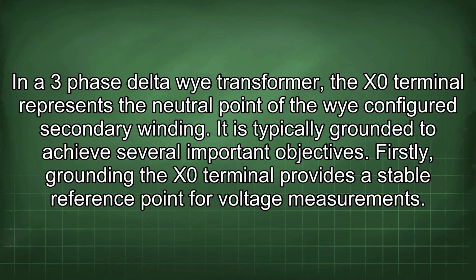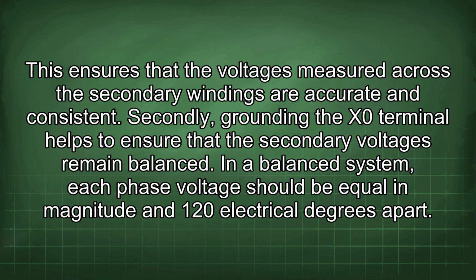In a three-phase delta-Y transformer, the X0 terminal represents the neutral point of the Y-configured secondary winding. It is typically grounded to achieve several important objectives. Firstly, grounding the X0 terminal provides a stable reference point for voltage measurements. This ensures that the voltages measured across the secondary windings are accurate and consistent.